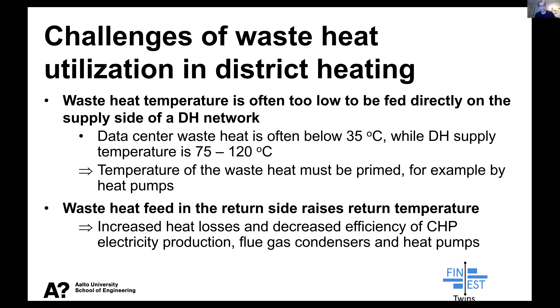In data centers, the waste heat is recovered from the cooling systems, and the typical cooling systems can be cooled by air or by a liquid cooling system or a combination of those two. Depending on the cooling system, the temperature is from 10 degrees Celsius to 60 degrees Celsius, and in an air cooling system the waste heat is cooler than in liquid cooling systems. What kind of cooling system the data center uses is affected, for example, by the size of the data center and whether there is a nearby possibility for natural cooling, for example river water or sea water, or if the outdoor air is cool enough for cooling the system.